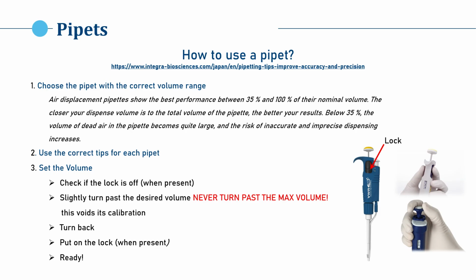The first important point when using pipettes is to choose the correct pipette for the volume you want to measure. A pipette's performance is best between 35% and 100% of their nominal volume. When taking up volumes under 35%, your risk of error increases. Second, use the correct tip for each pipette. Even though different tips may fit on the same pipette, their performance is best with the correct tip attached.